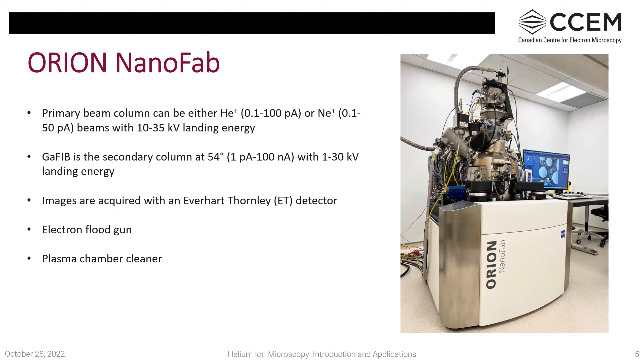This instrument is a dual ion instrument with two columns, similar to a FIB-SEM. In the primary vertical column, you can use either a helium or neon ion beam. At 54 degrees from that is the secondary column, which is the gallium Canion focused ion beam used by Zeiss on other FIB-SEM instruments. So you have access to three beams. An important feature is the electron flood gun, which neutralizes positive charge accumulation on the sample.